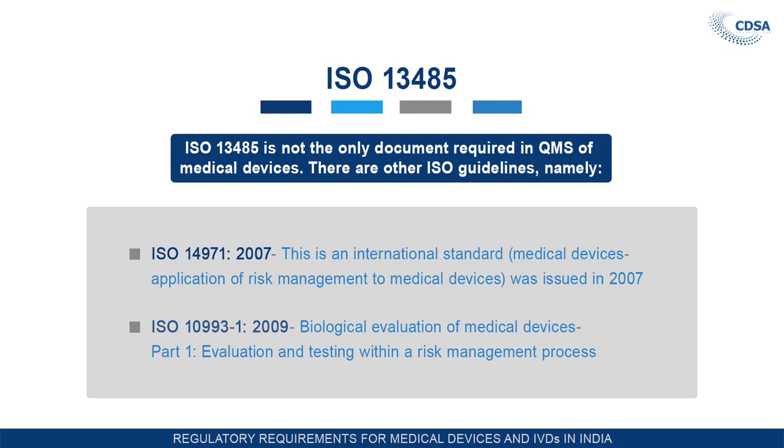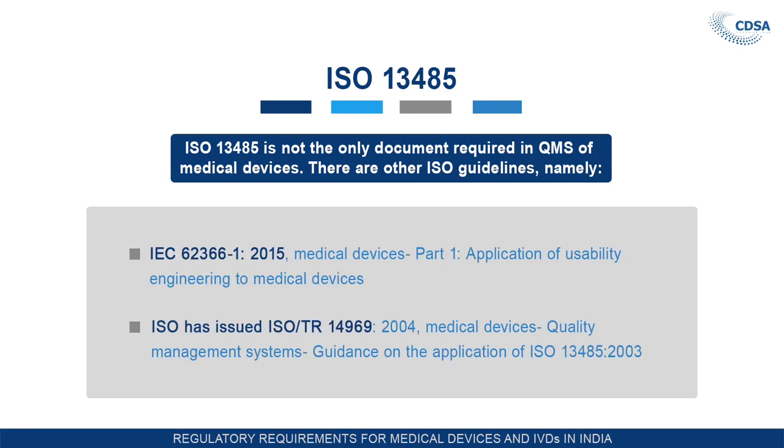ISO 10993 is the biological evaluation of medical devices. If the medical device has to be evaluated biologically, then this ISO is required to be applied. IEC 62366 is the application of usability engineering to medical devices. This is basically engineering, a portion under ISO 13485.